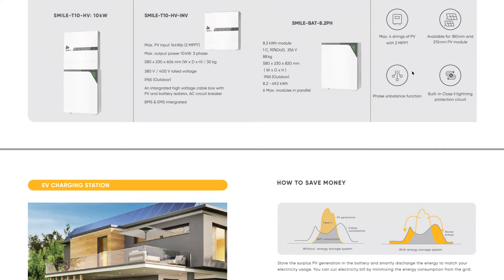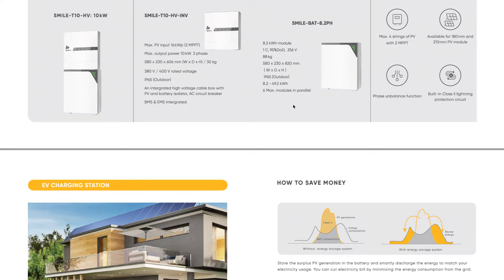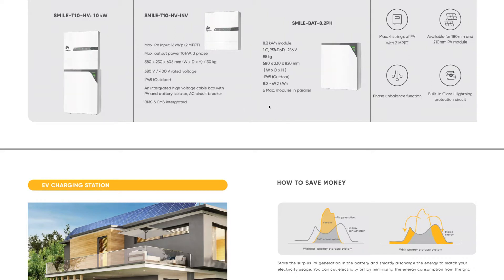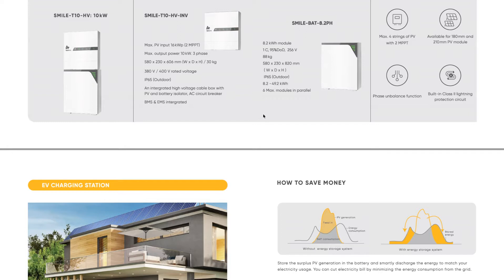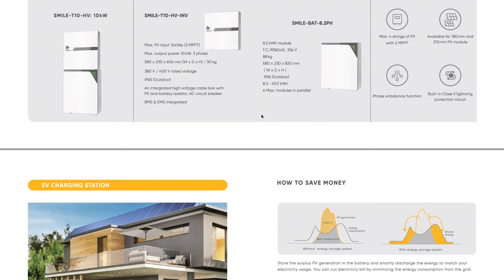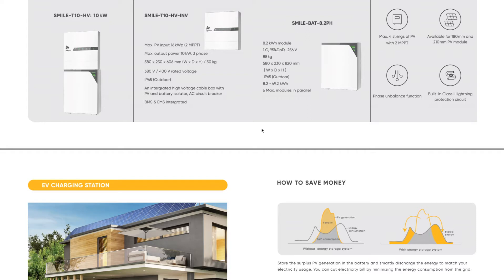And then we have the phase balancing function, and then we have some extra protection. You can also oversize a lot more on this system. The inverter is rated at 10 kW DC AC. That's the maximum it can output, but it can actually connect I think 16 kW. So you can oversize by a lot, and it's meant to be oversized. Which creates an enormous gain in value for money with this new model. How much we have to look at every installation to see how much we should oversize, but the oversizing is definitely easier and better and more stable with this new version.